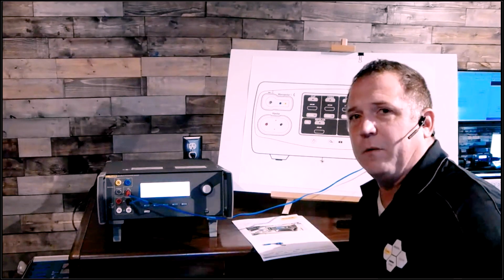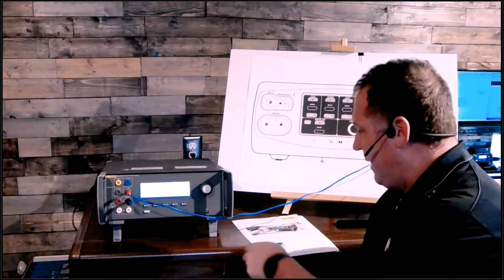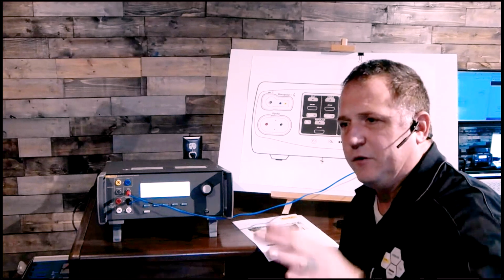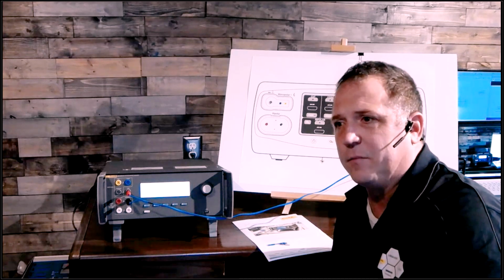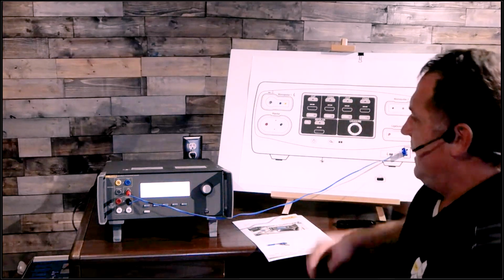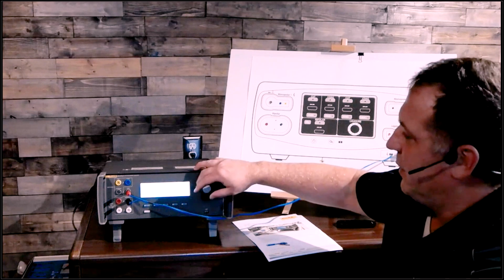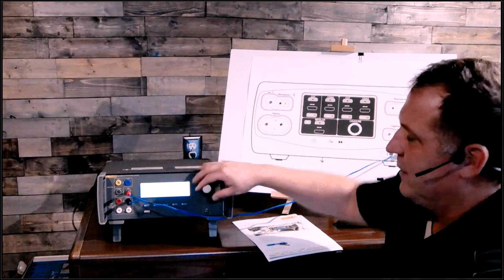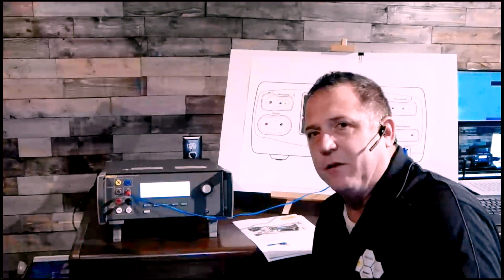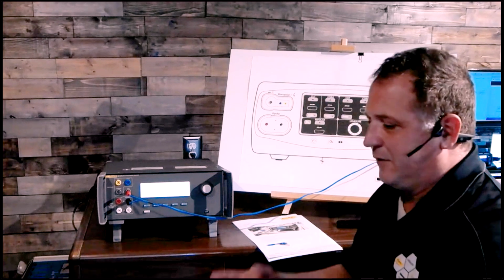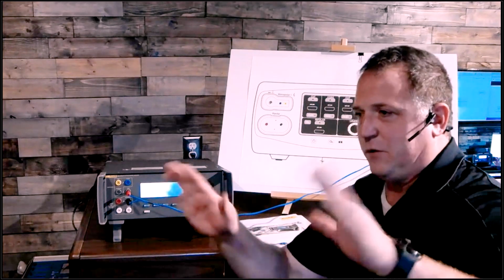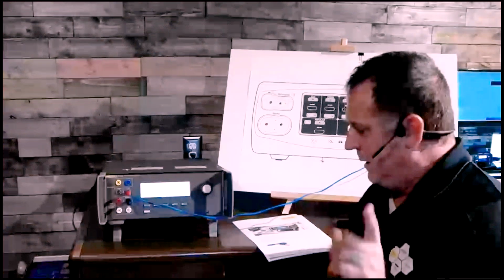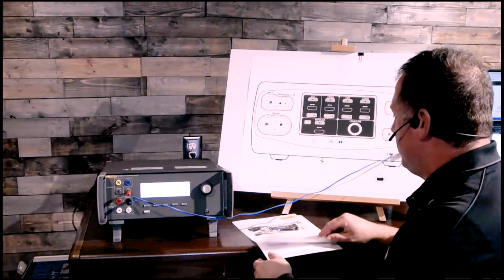And then you know at what resistance your ESU high end of your CQM is set for, usually right around 135 ohms, plus or minus 2 or 3. And again it's going to have you test way down low, somewhere around 7 or 8, to see where the low end of that resistance spectrum is. That measures the resistance between the 2 foils attached to the patient. We'll talk more about that if we have time.